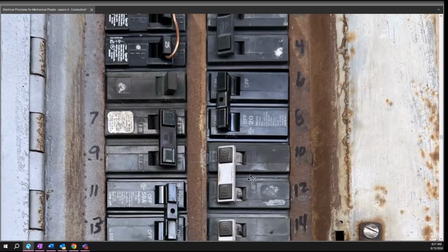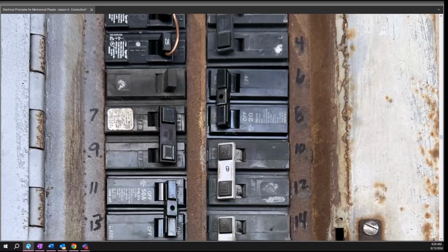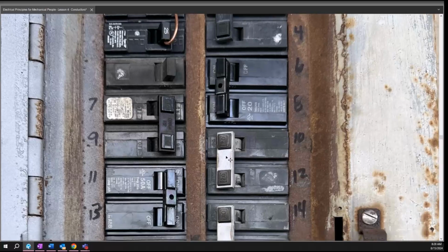These are 2 single pole breakers connected by this little bar. This is a totally legal install, as long as they have a permanently affixed device to turn off both at the same time. This is legal because it's a single pole breaker feeding a single phase 2 pole load.